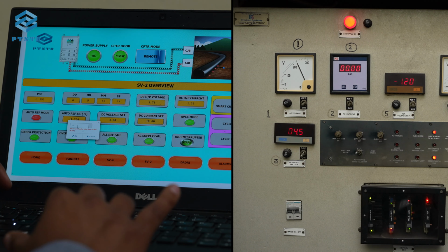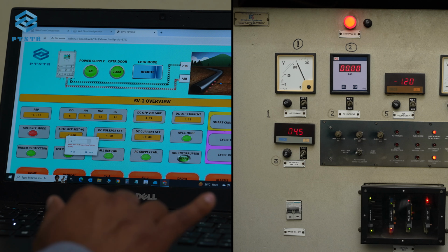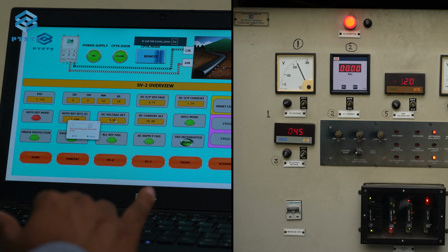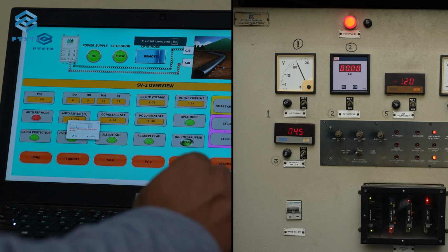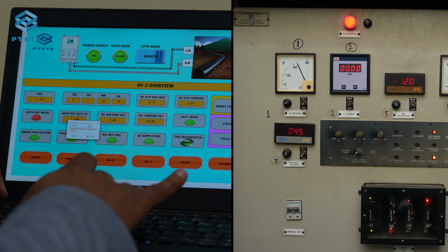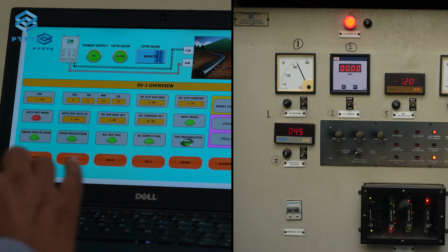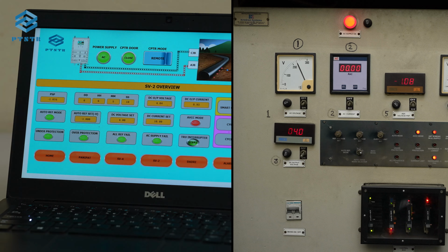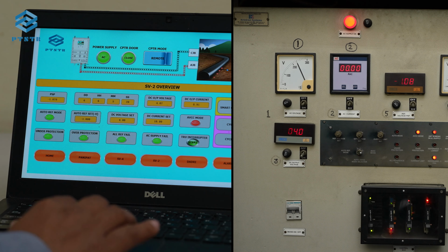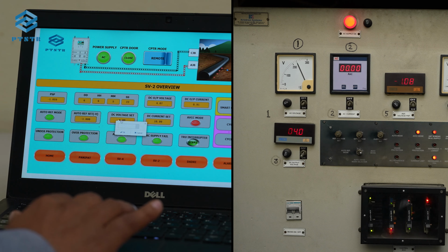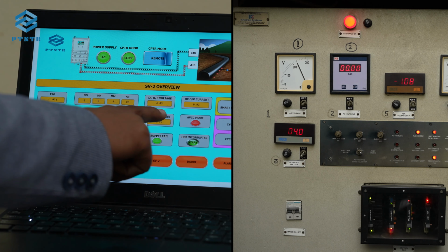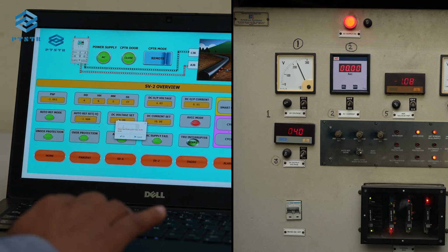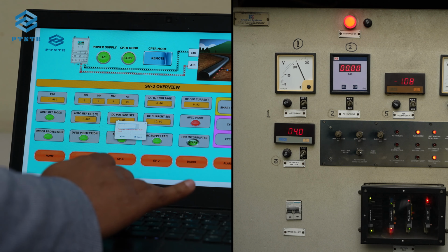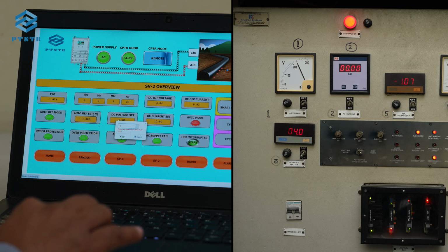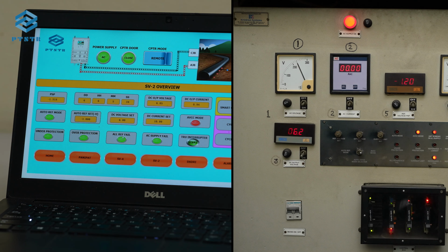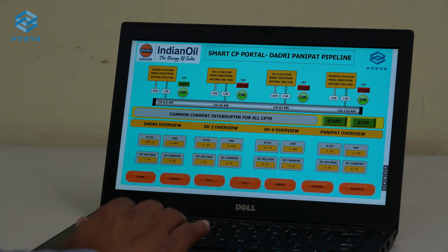Let us see how the values are changed in real time. With change in reference PSP from minus 1.2 volt to minus 1.45 volt, we can see the reading getting automatically updated in real time in CPTRU. Similarly, with change in DC voltage from 4 volt to 6 volt in the system, we can see the reading getting automatically updated in real time in CPTRU. We can change all other parameters in real time. This is the unique feature where we can set all 4 interrupters simultaneously through remote.